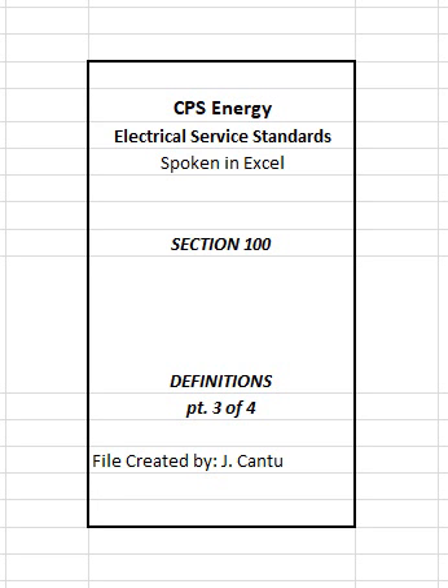Exception number 2. Where an auxiliary wire gutter is sized to a minimum of 16H×8D and is used to supply not more than 2 residential dwelling units or apartments, an external junction box is not required and the point of delivery will be in the auxiliary wire gutter. Exception number 3. Where step bus gutters meeting CPS Energy specifications are used by customer and length is adequate to supply the maximum number of meters that may be supplied from the gutter, an external junction box is not required and the point of delivery will be at the bus gutter.